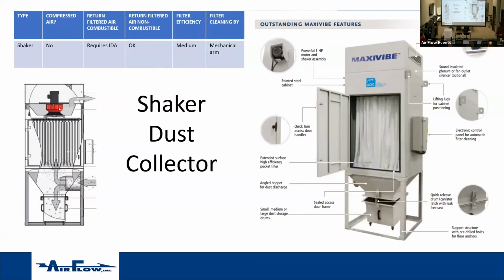A shaker will do the same type of system. So the dirty air is going to come in through the shaker. It'll have a little drop out here. There's an instantaneous drop in pressure as the velocity drops out. The heavier particulate will fall down into the collection. The lighter particulate that still stays friable in the air will come up and get picked up by the filters, and the clean air comes out. In this scenario, there is a plate or an arm or a device in here that will actually shake, called a shaker. It'll shake itself, and that shakes all of the particulate that stays in the filter media and drops it out. So it's self-cleaning. A shaker, like a cartridge pulse, is a self-cleaning device.